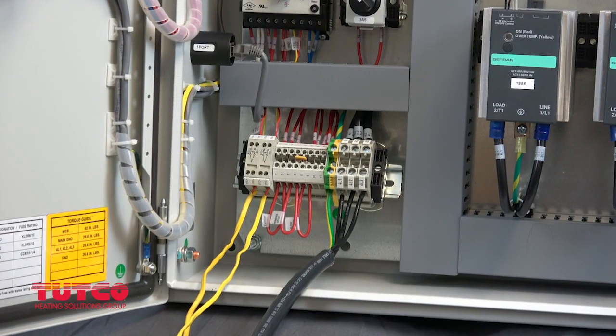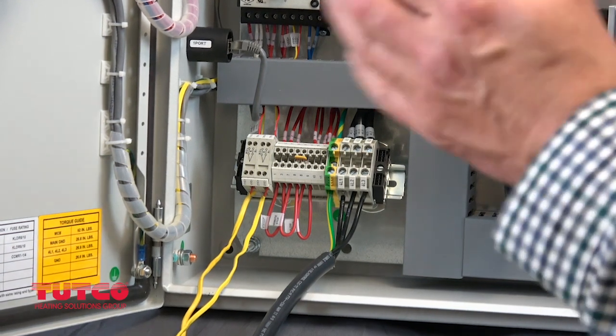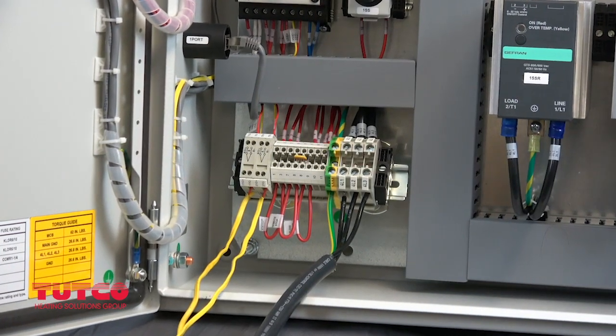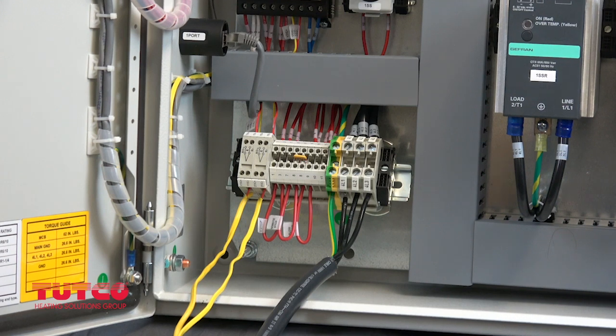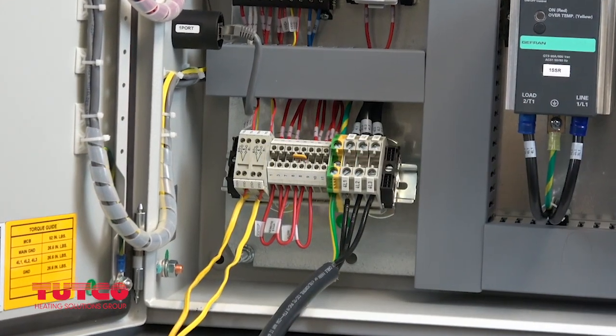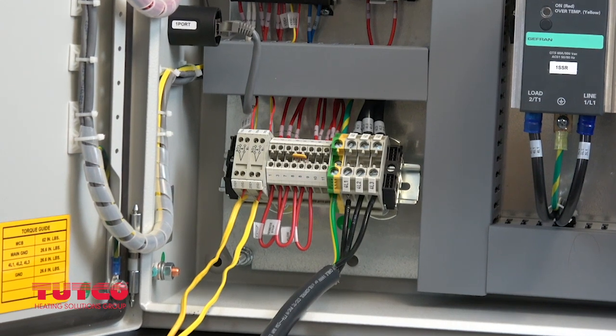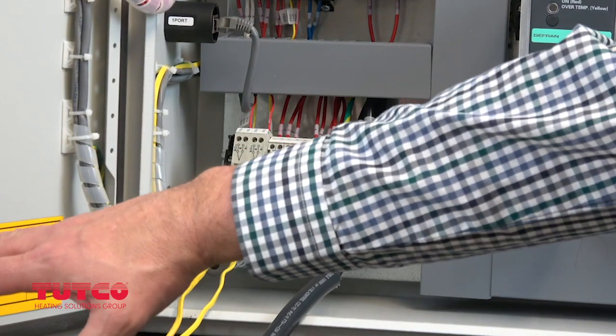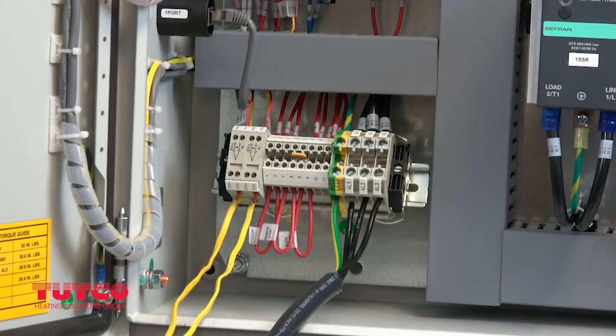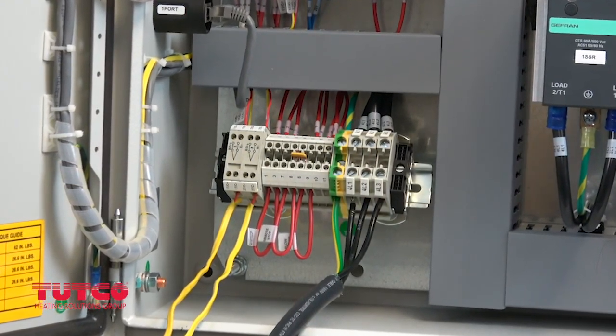The final step in wiring is the remote control and application-based connections. The controller can be run at the panel or remotely from a push-button station or PLC. There are 5 customer interface connections. The labeling instructions for these connections are on the inside of the door panel. There is an e-stop, a remote stop, a flow sensor connection, and a remote start.